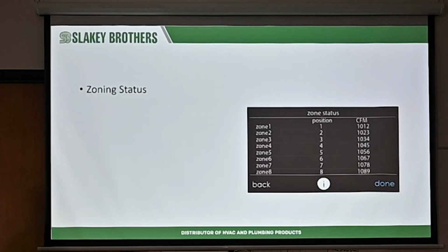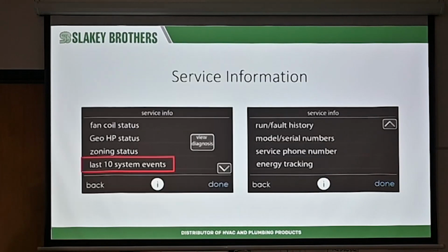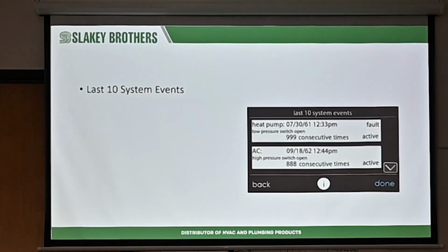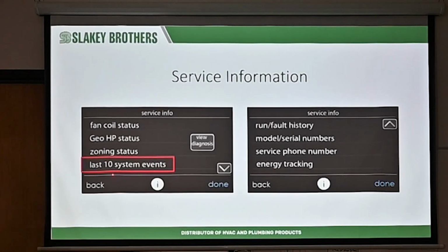Same thing with zoning status, what the zones are doing. We know these numbers are fake because there's no way you're getting 8,000 CFM out of a unit. And again, besides the last 10 system events, there's run fault history. This is where you can find the actual faults for the heater, actual faults for the heat pump, actual real faults that are in memory. And at that point you can delete them if you want, so you have fresh data next time you come back.